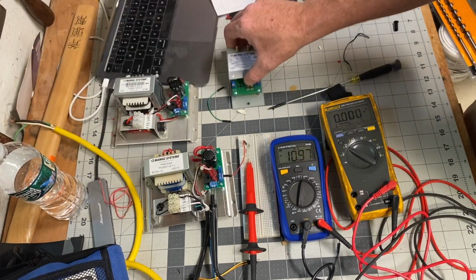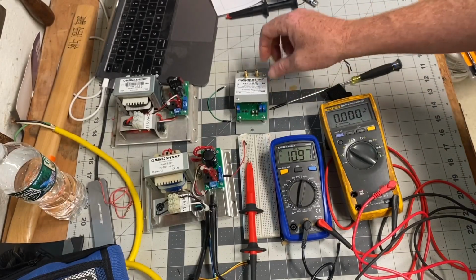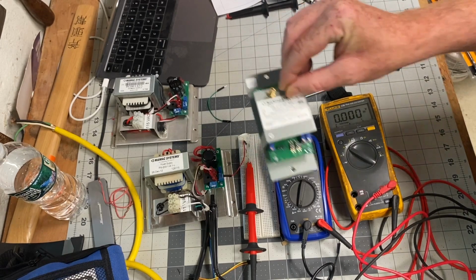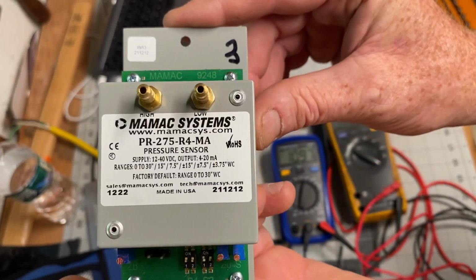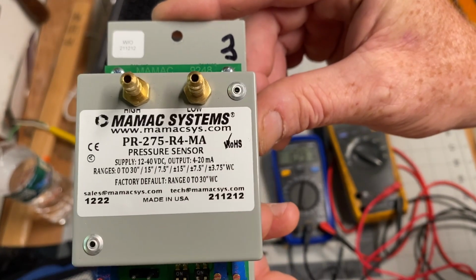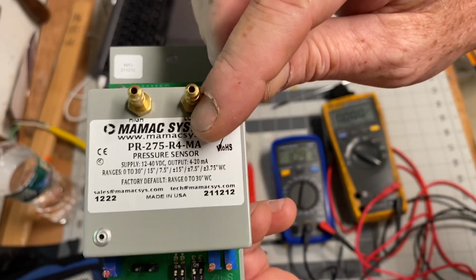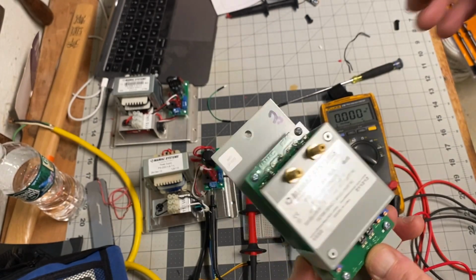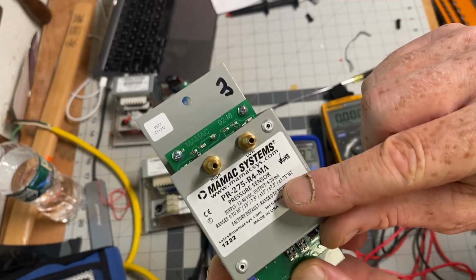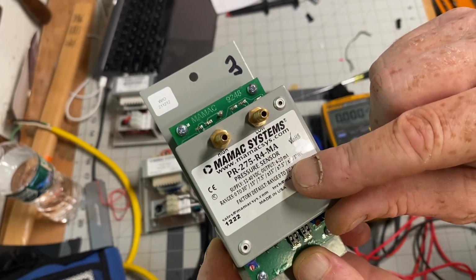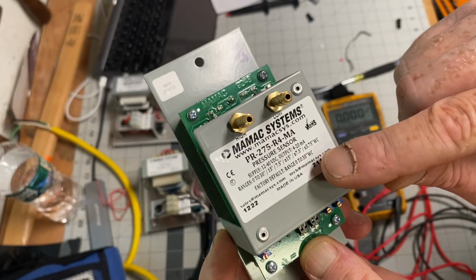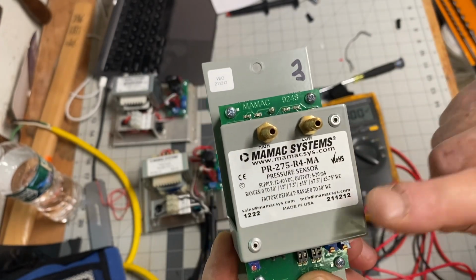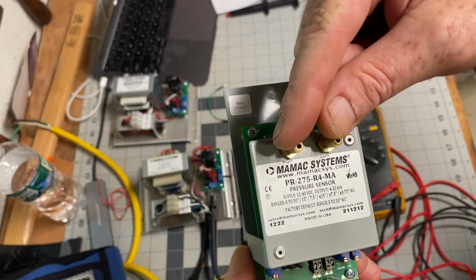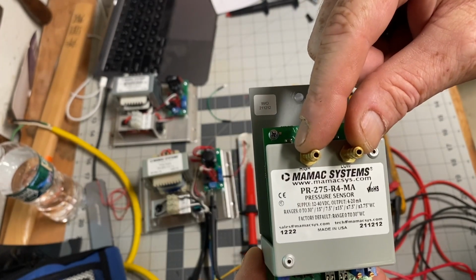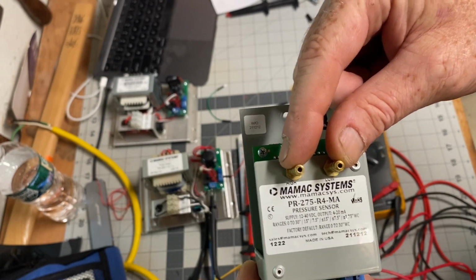The other thing I kind of want to look over is these static pressure sensors, these Mamac sensors. Maybe I'll do a different video on these, but it was a slightly different one we were using for the building pressure. I think they got an R3 version that will read down to plus or minus 0.25 inches. This one will do plus or minus 3.75 inches. These we've been finding a lot on rooftop units that are measuring CFM across the fans. They're measuring the velocity pressure, which gives them essentially a CFM that the fan is outputting.